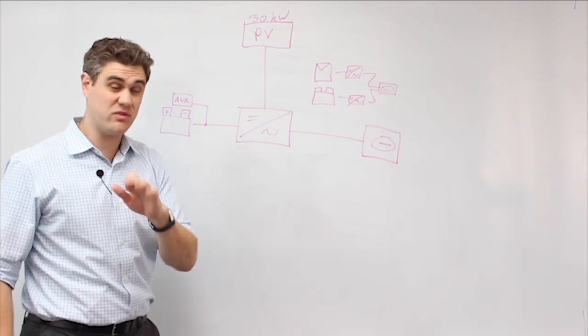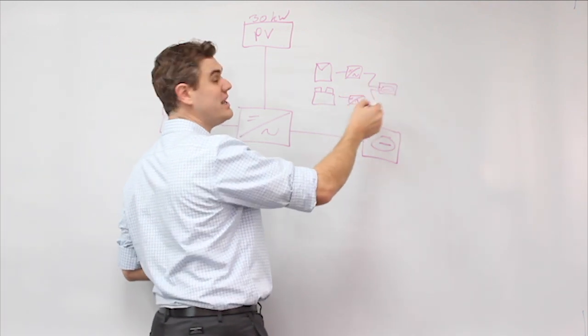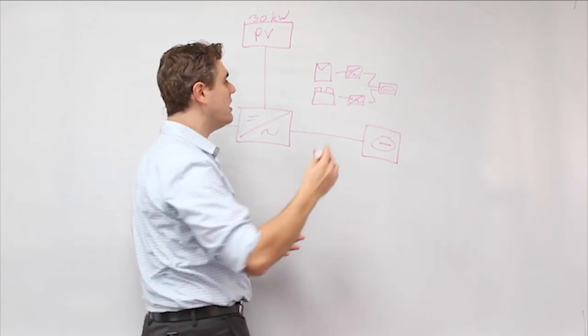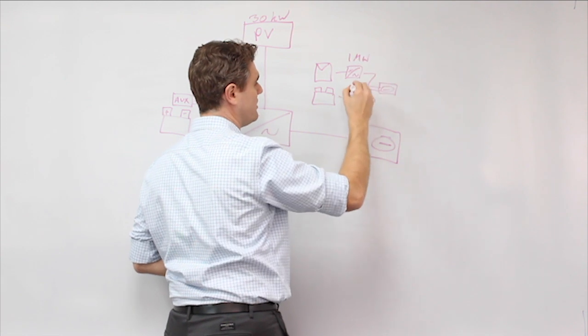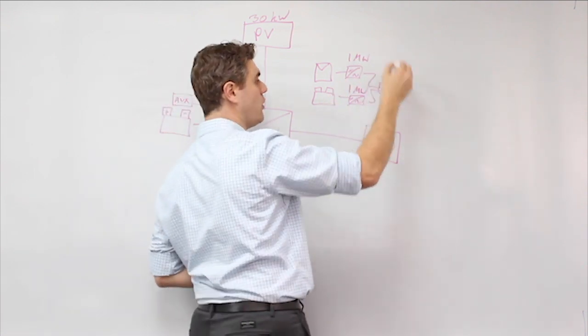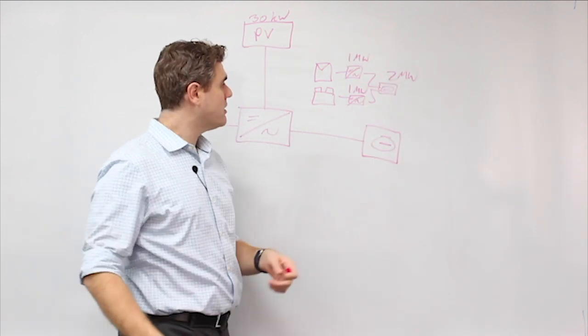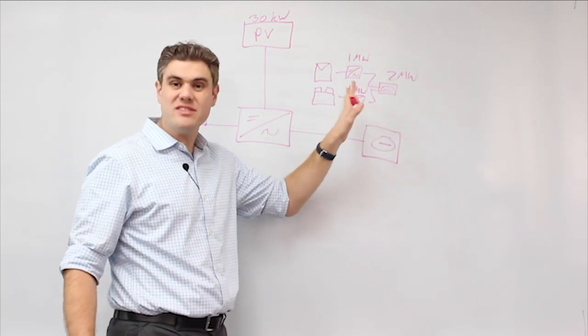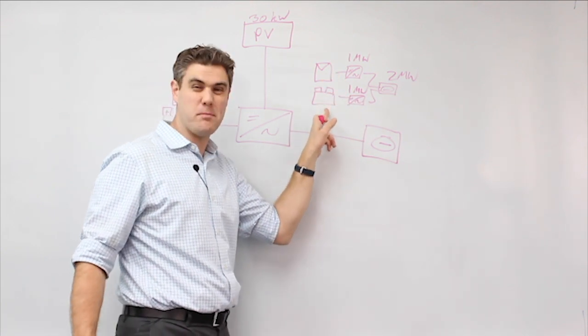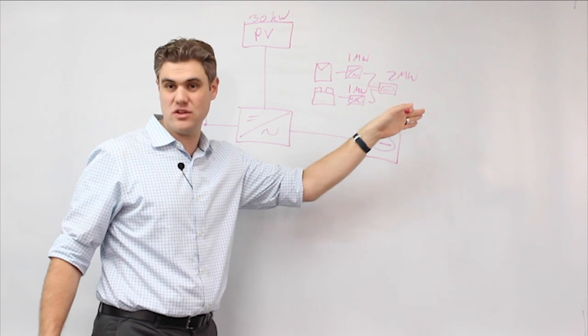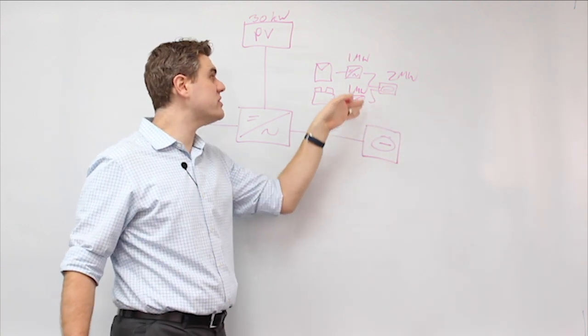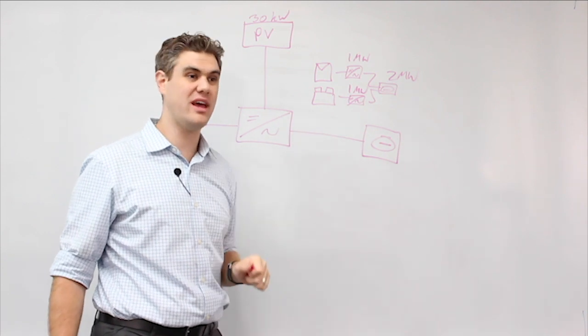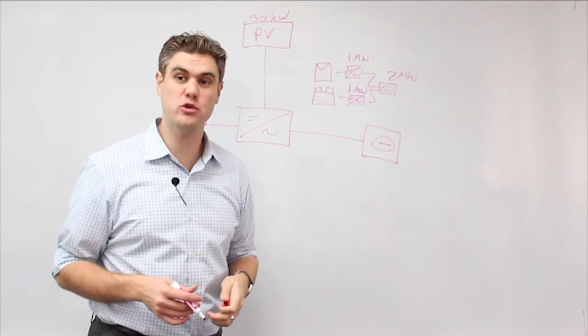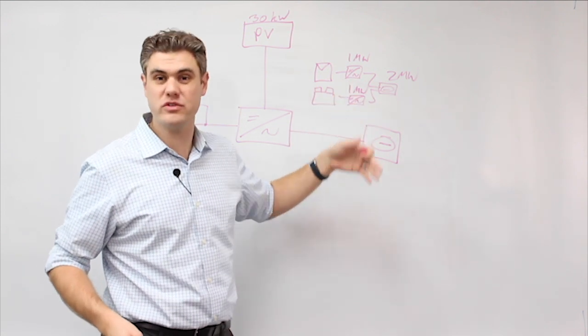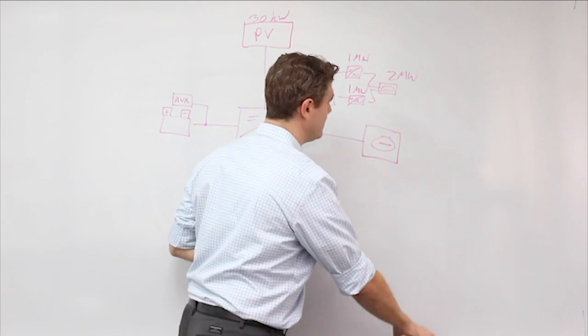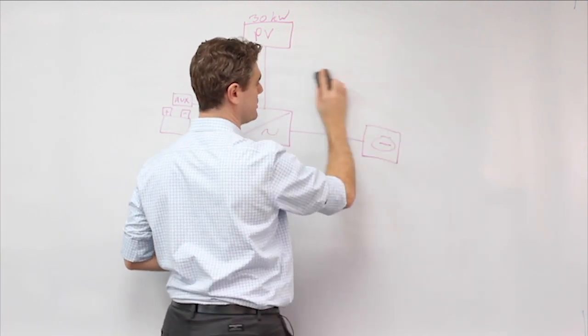And from the utility's perspective, this will become more important later. The utility, when they rate the system, when they evaluate its size, if this is a 1 megawatt size inverter and this is a 1 megawatt size inverter, they will call the total system 2 megawatts. So this is a bigger system. And it's not exactly fair because, like I mentioned earlier, you're never going to really want to export this battery into the grid. You don't want to do that necessarily. But yet the utility will see 2 megawatts worth of inverters touching their grid, and they will say, you could, in theory, export 2 megawatts. There's nothing preventing you. So I'm going to call this a 2 megawatt system. And so that can be problematic if you're trying to stay under certain constraints. We'll come back to that.